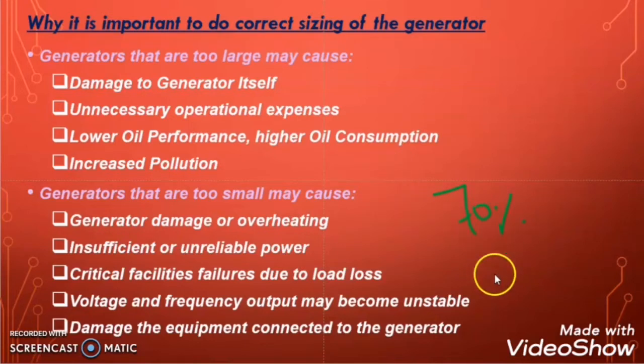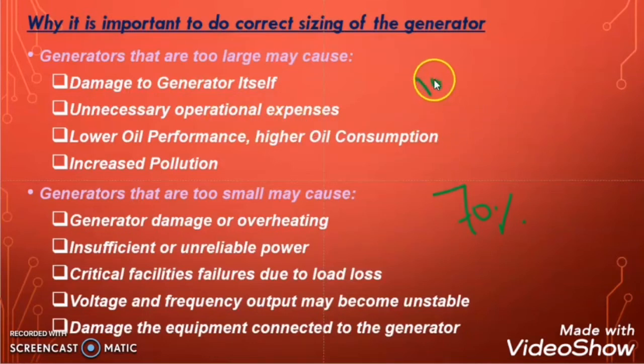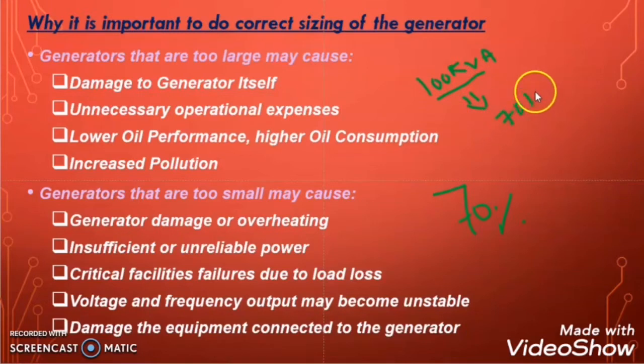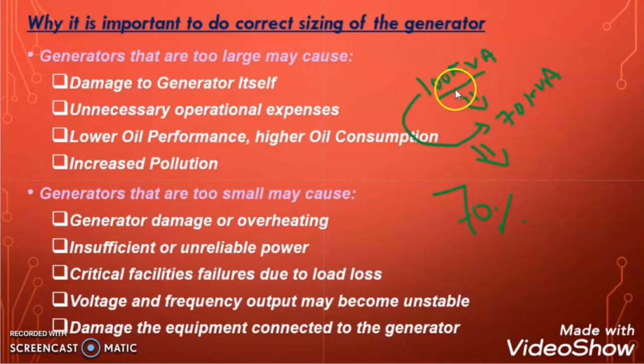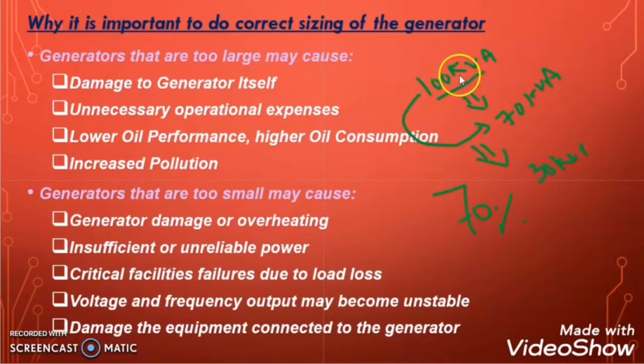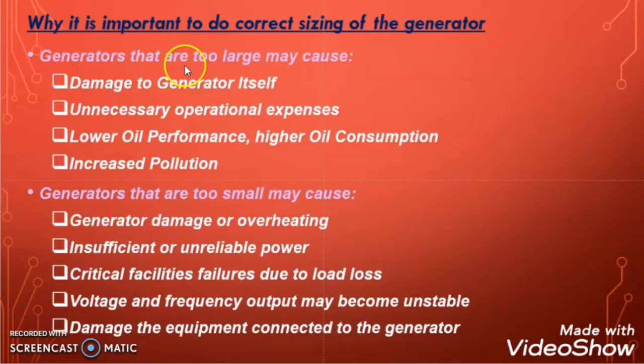The oversized generator will always run in an under-loading condition. Suppose you selected a generator of 100 kVA — when running, it should process a minimum of 70 kVA load, because 70% of the selected kVA rating must be present when the generator is operating. But if you selected an oversized generator and the actual load is only 30 to 40 kVA, then the load on the generator is very low — that condition is called under-loading. Due to the oversize selection, the generator is in under-loading condition, and due to under-loading it will damage itself.